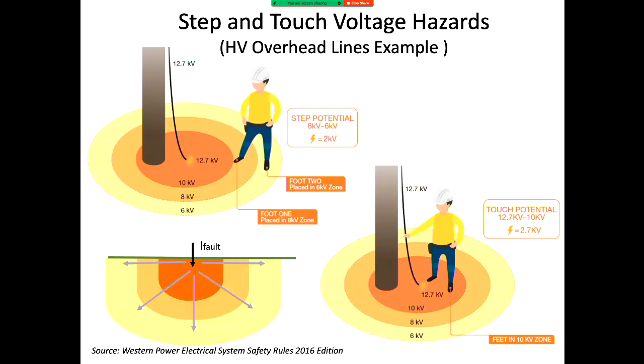Now if you touch something, you might think that's obviously bad, but what's actually happening is all to do with the relative voltage between your feet and your hand. So it might be 12 kV at your hand but 10 kV at your feet, and that difference gives you a touch voltage. This is very important when you start looking at substations and things like that.